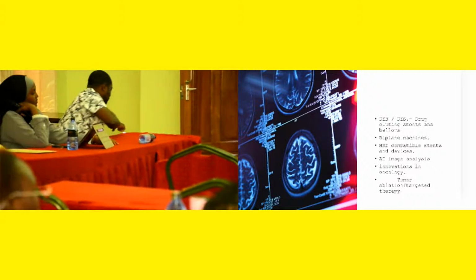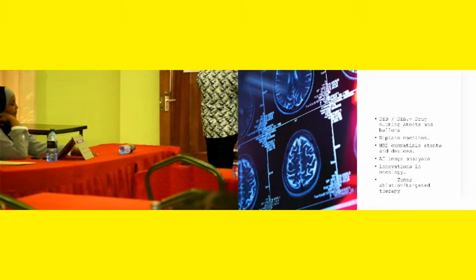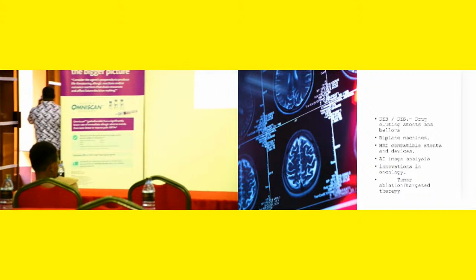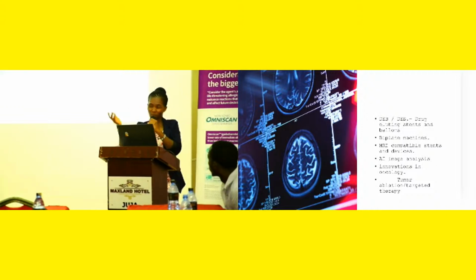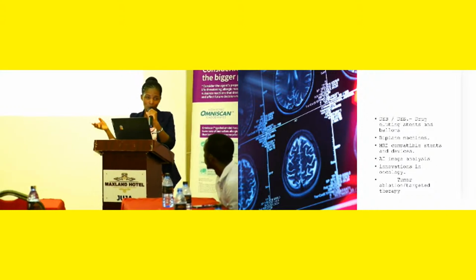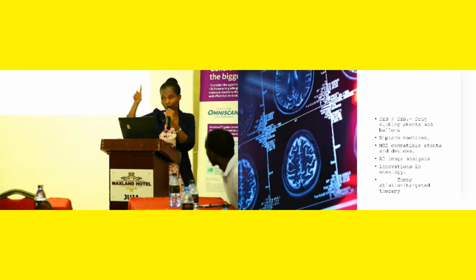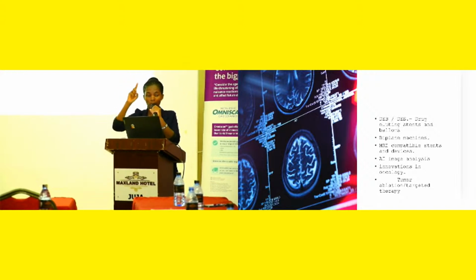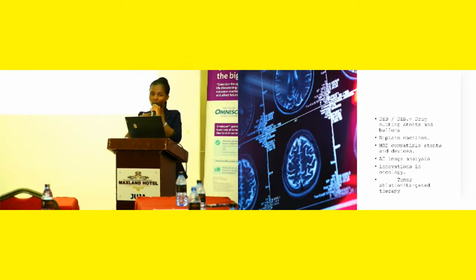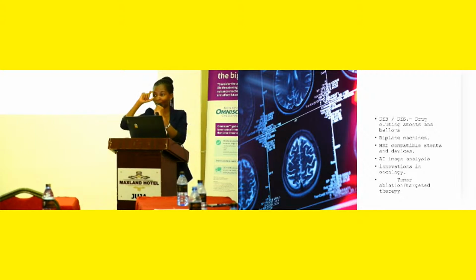Thank you. I like that question. The cath lab unit does not only have the shields that we wear in X-ray. We have ceiling suspended shields. We have mobile shields. We have bedside shields. There's also the factor of distance. So those people close to the C-arm, one, I put on the lead gown, the thyroid shield, the glasses, right?